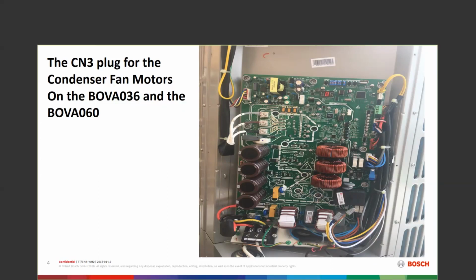One of the issues behind this board is that if I turn the power on, electrify the board, and then I want to do something, change the board, check something, I may want to turn the power off, pull the disconnect. That screen up there is going to go black, but that doesn't necessarily mean that those brown DC capacitors have dissipated their voltage. They can hold it for a while. There's nothing on the board to dissipate that voltage. You can't take a screwdriver like my dad used to do and short across the board to dissipate the voltage. You just have to wait a little bit.